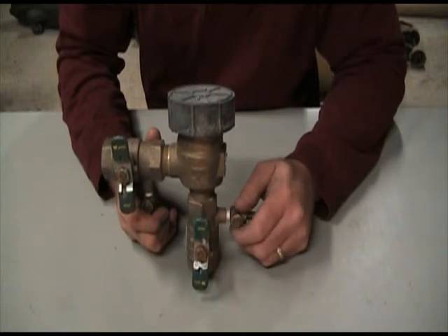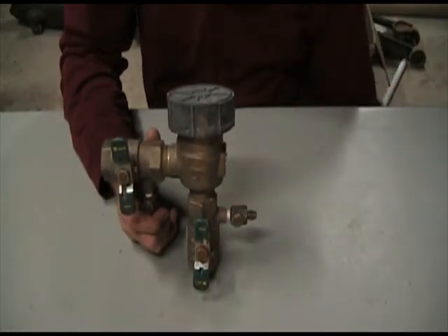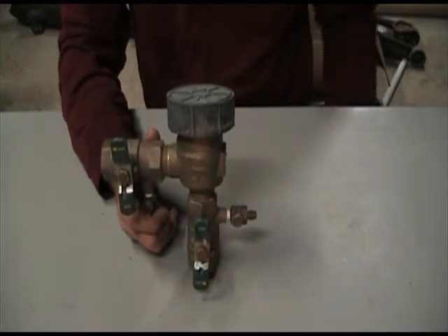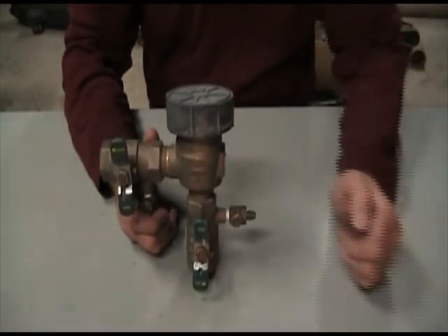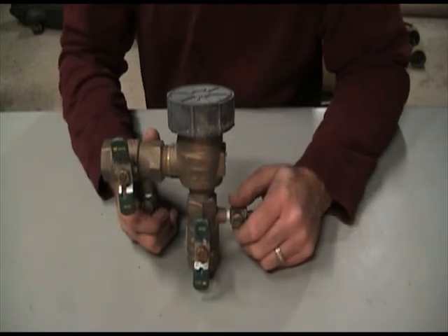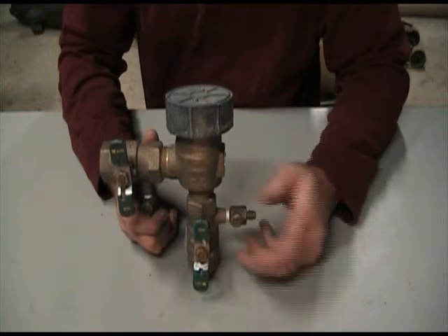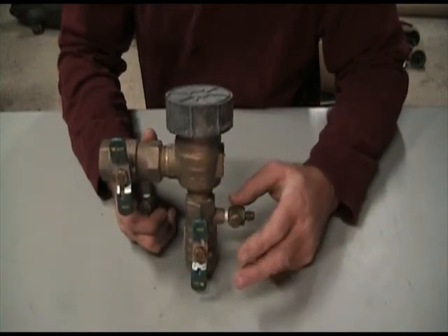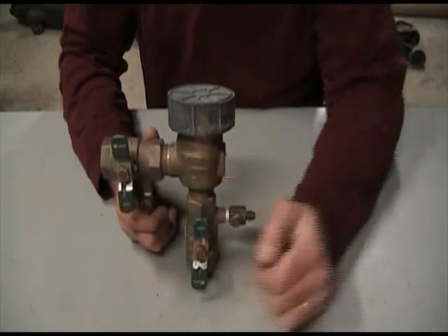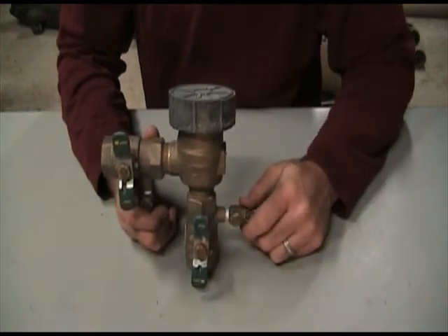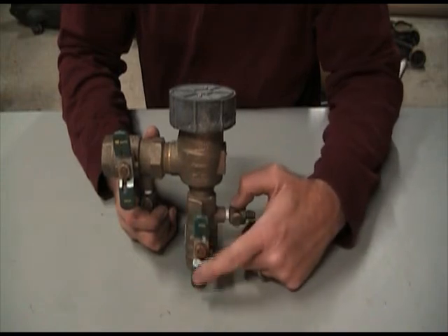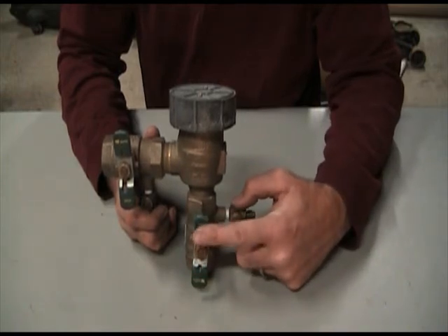These are very important. And most of your municipalities in this country require you to have some sort of anti-siphon valve or check valve in your sprinkler system. Now with this one here, this is called an 800 M4. It's a 1-inch backflow preventer. As you can tell, it has two ball valves. And I'll point something out about a ball valve. You can see how this handle is in line. That means that it's on.